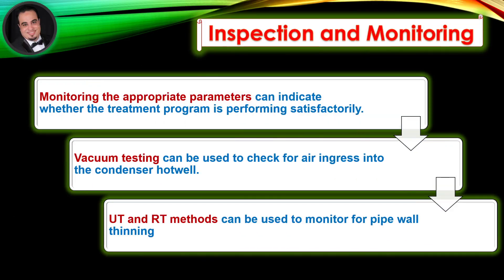Inspection and monitoring. Monitoring the appropriate parameters can indicate whether the treatment program is performing satisfactorily. Vacuum testing can be used to check for air ingress into the condenser, as well as UT and RT methods, which can be used to monitor for pipe wall thinning.